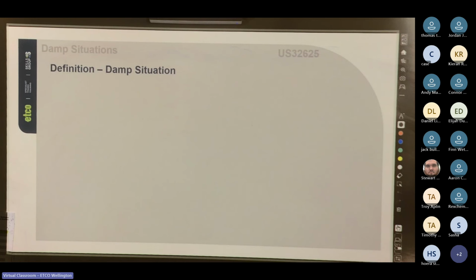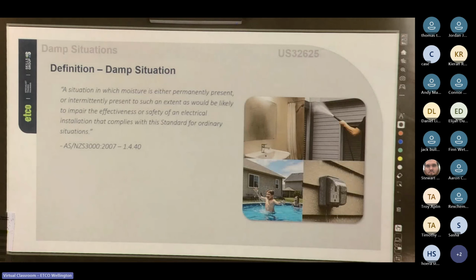Cool. So, some definitions. It's defined in 3000 as a situation in which moisture is either permanently present or intermittently present to such an extent that it would be likely to impair the effectiveness or safety of an electrical installation that complies with this standard for ordinary situations. So, we'll look at a few examples, but a damp situation isn't just water pouring directly onto the equipment. It includes condensation, steam, and splashing. Think of steam in a bathroom or a kitchen, or a kitchen bench near a sink. All of these reduce insulation strength and make shock more likely.